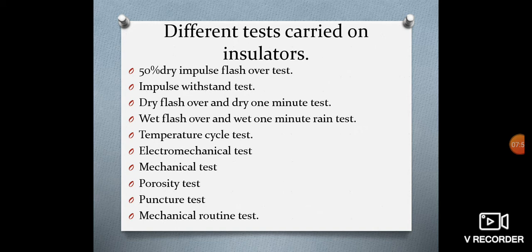The insulator with 50% of 1 minute rain test voltage applied to it is then sprayed for 2 minutes. The voltage is raised to the 1 minute test voltage in approximately 10 seconds and maintained there for 1 minute. The voltage is then increased gradually till flashover occurs, and the insulator is again flashed at least 4 more times. The time taken to reach flashover voltage is in each case about 10 seconds. The flashover voltage must not be less than the value specified in the specifications.